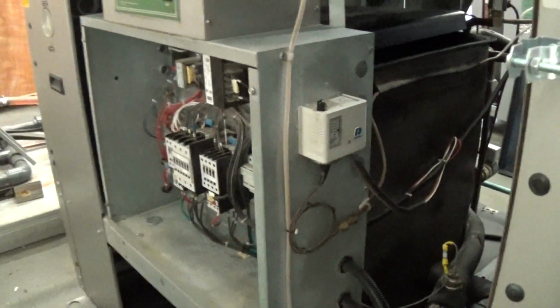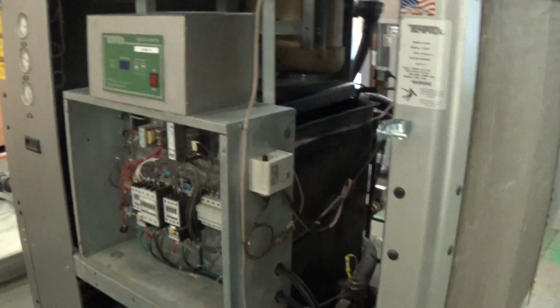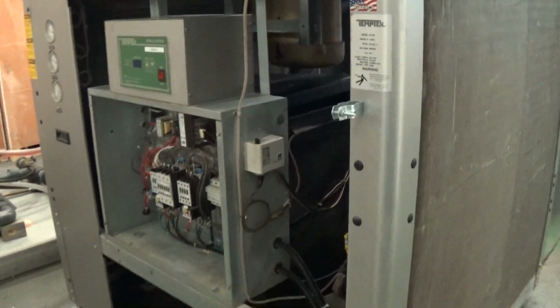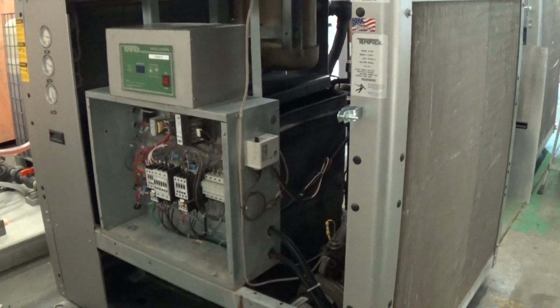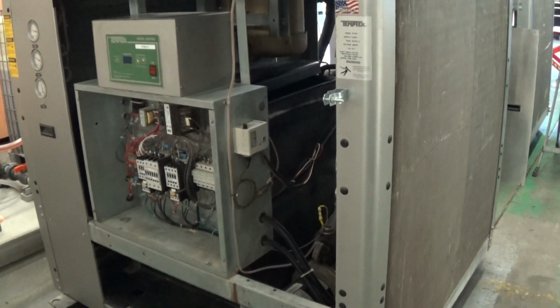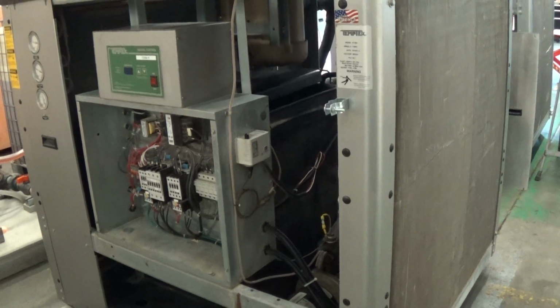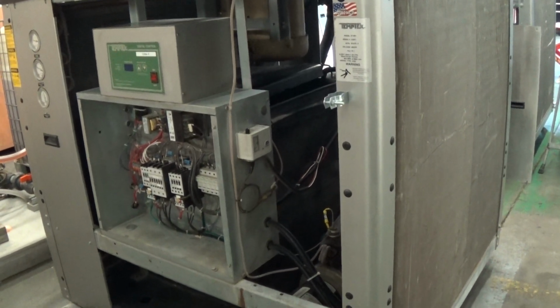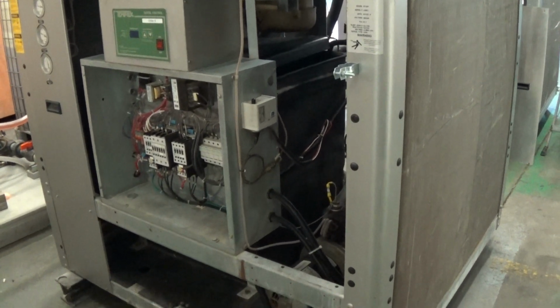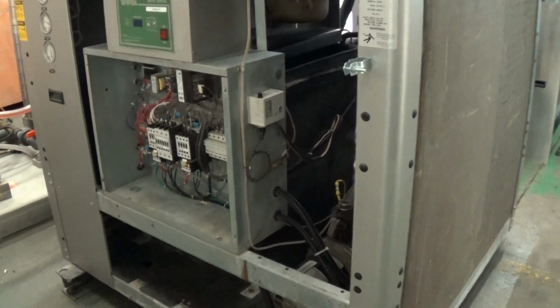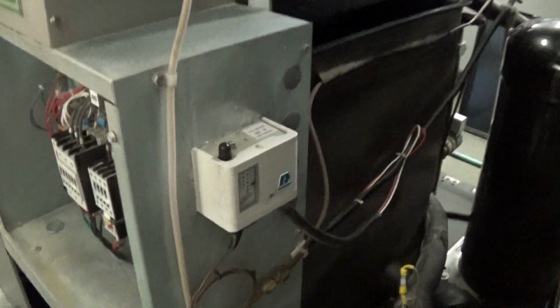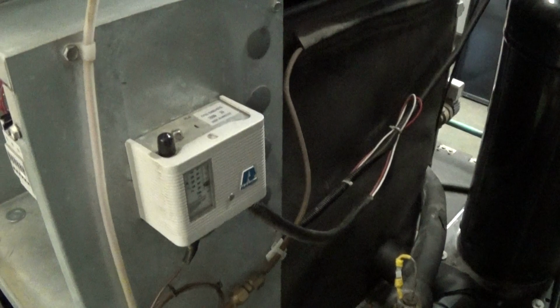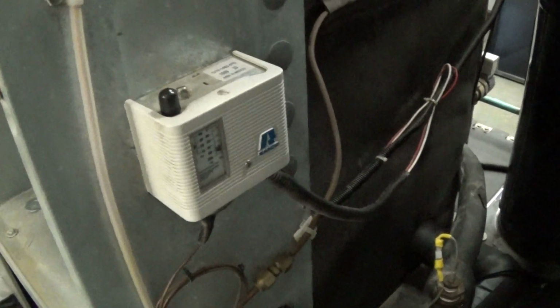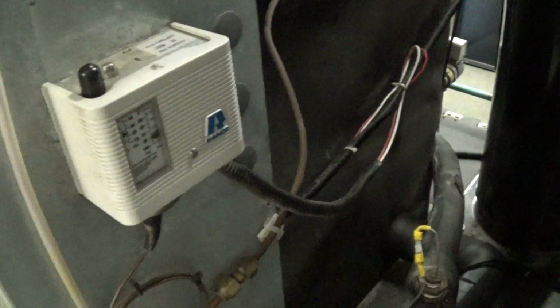So we're going to come back and run this thing after I get the side covers on. It's going to be very, very quick because of this short amount of water. We're going to be able to bring it down from approximately 85 degrees to 45 degrees pretty quickly. Oh, one last thing while I have the covers off. This is your low pressure reset. Low pressure should only be tripped, and this is an auto reset.